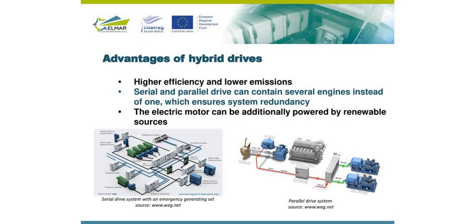As yesterday, I would like to remind some advantages of the hybrid system. It can have a higher efficiency and lower emission. We can have different configurations, and what can also be important, we can have other sources of additional supply. The sources can be renewable. One additional advantage is that we can have redundancy in this system. It means if one engine or genset is faulty, we have another genset and we can use it. We can also have a spare emergency genset, which can be used for occasional situations.